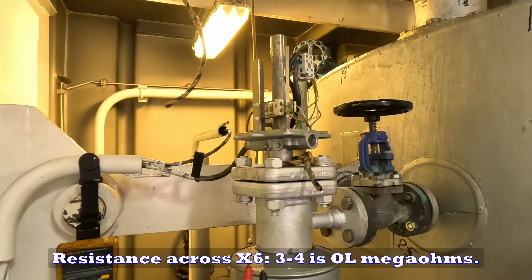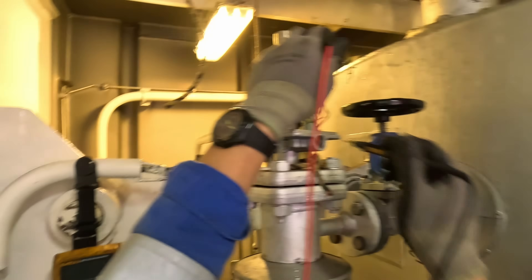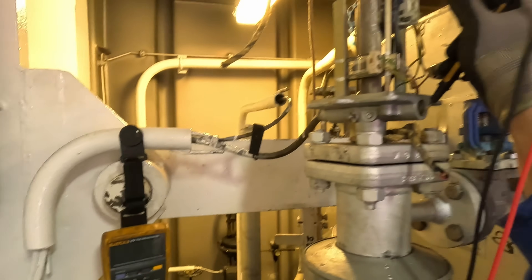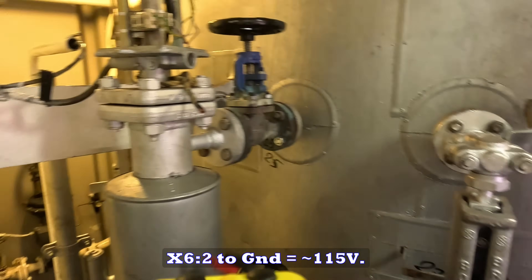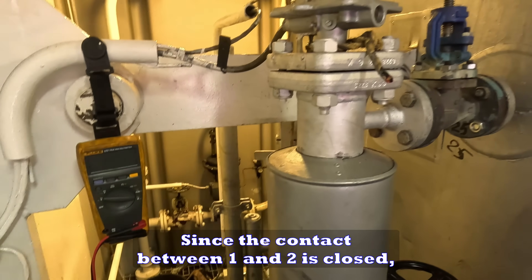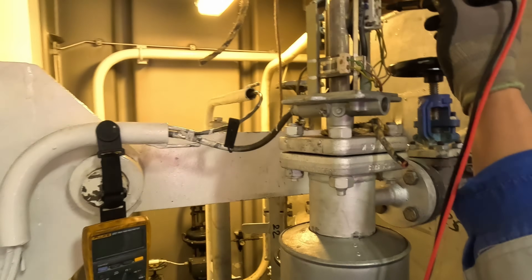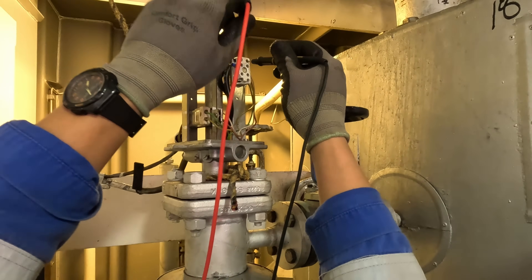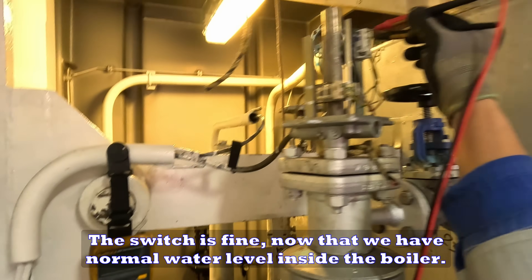Resistance across X6 terminals 3 to 4 is OL mega ohms — also good. This side is normally open. Voltage from X6 1 to ground is around 115 volts AC, and X6 2 to ground is also around 115 volts. Since the contact between 1 and 2 is closed, both terminals have nearly the same potential to ground. The switch is fine now that we have normal water level inside the boiler.